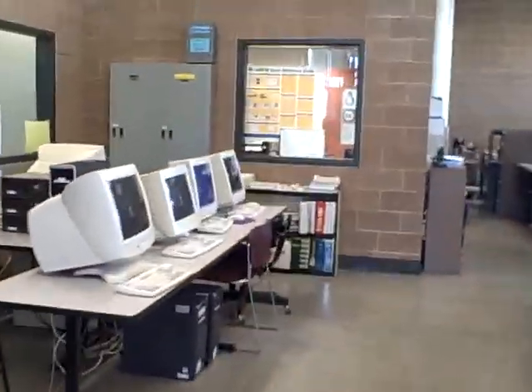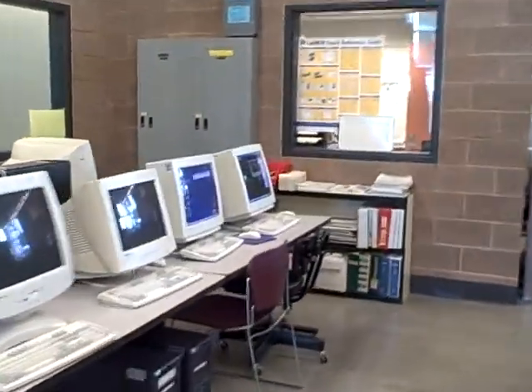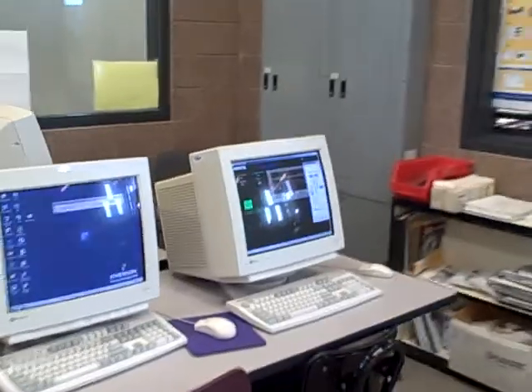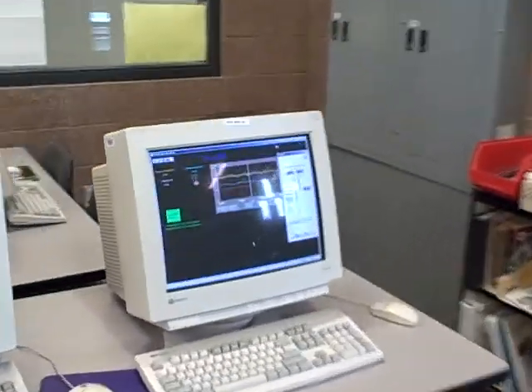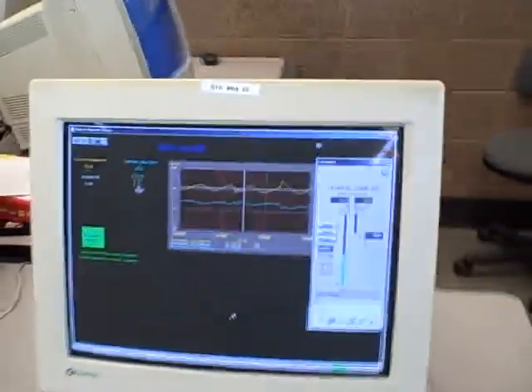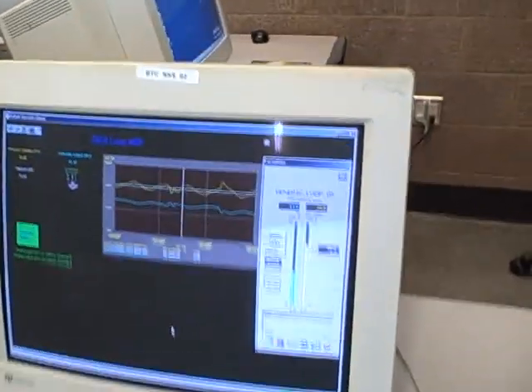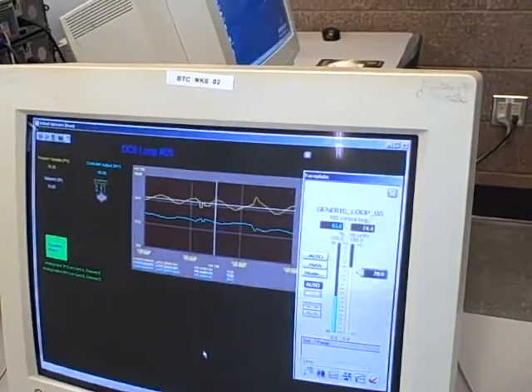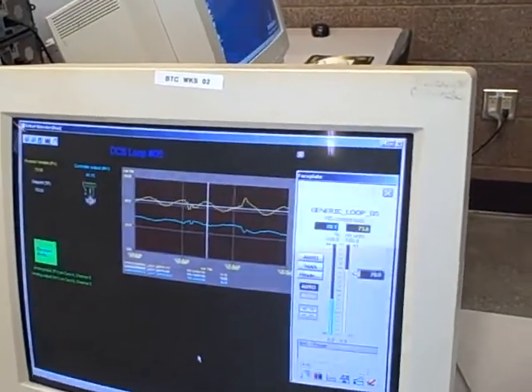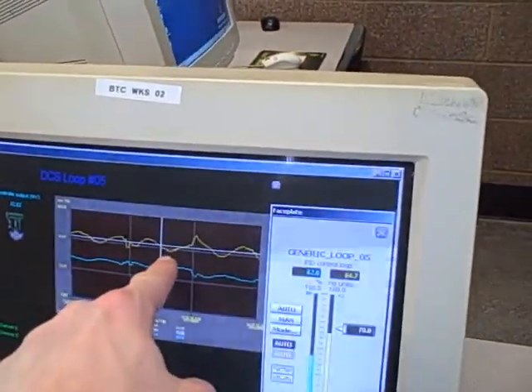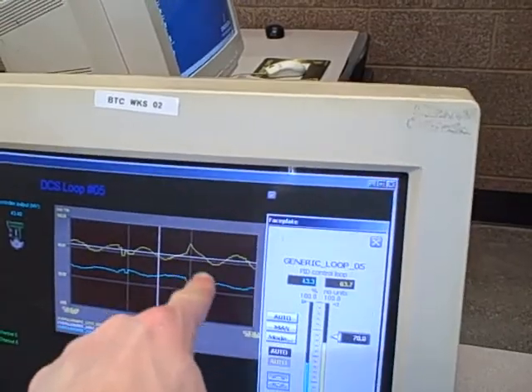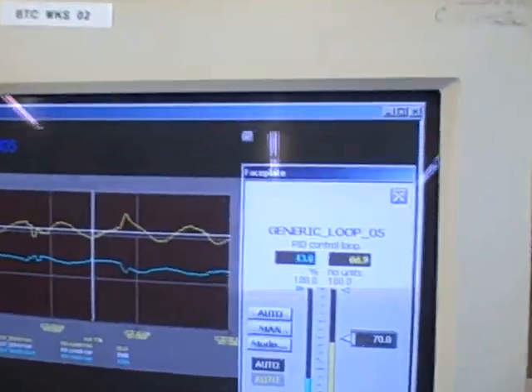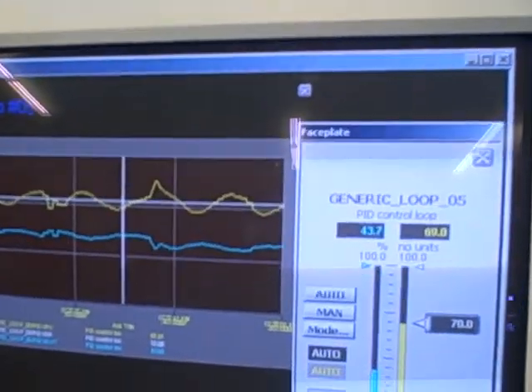But in turning that air pressure up, I've now changed the dynamic of the system. The system now has a higher gain, so overall I have more of a tendency to oscillate than I did before. And in fact, we're beginning to see a little bit of that right here. As I turn the gain up, we're seeing a greater oscillation up and down around setpoint.